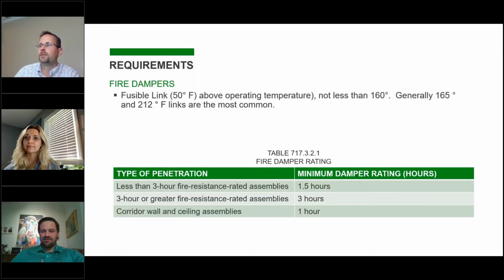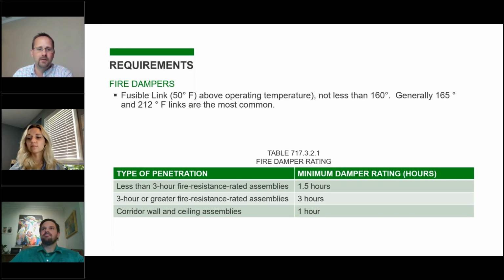So I'll just say, yeah, in one of our previous slides, we showed, I can present real fast. So this slide shows that if it's a less than 3 hours rated assembly, your damper has to be at least 1.5 hours. If it's 3 hours or greater, it's 3 hours, and corridor walls or assemblies are just 1 hour. So that corridor damper that we briefly spoke about is like that 1 hour assembly, but that's why they call it a corridor damper, because you wouldn't use that anywhere else. But I would say 95, 99% that we see are going to be 1.5 hour dampers, because we don't see many walls that are over a 3 hour rating.